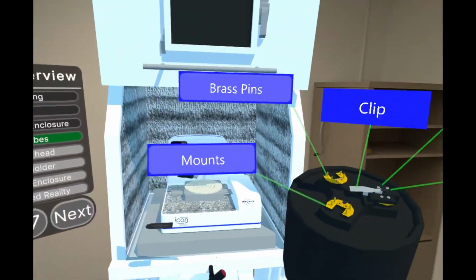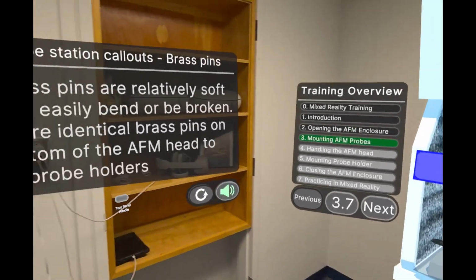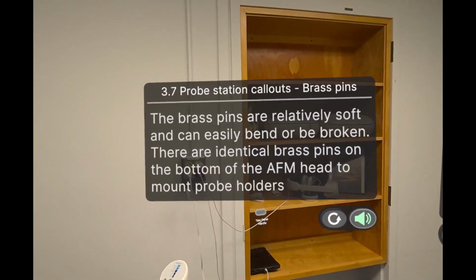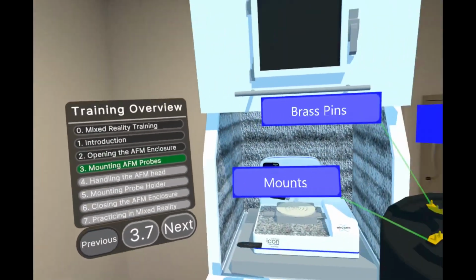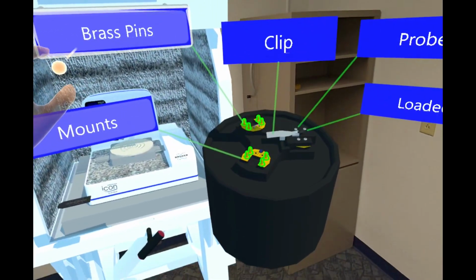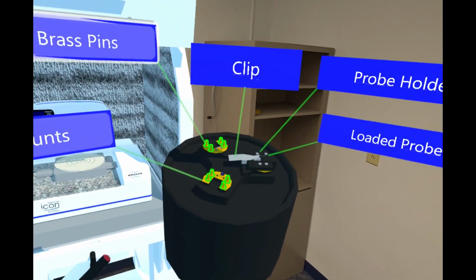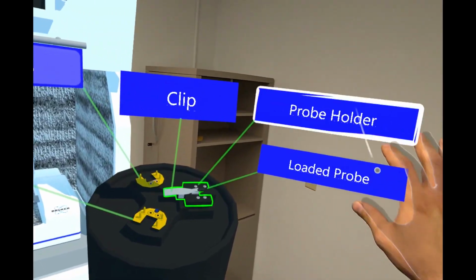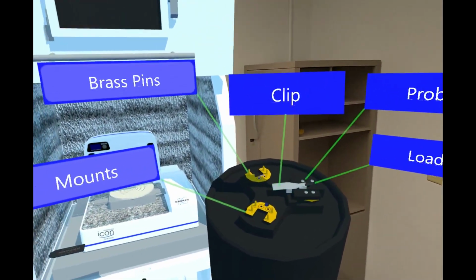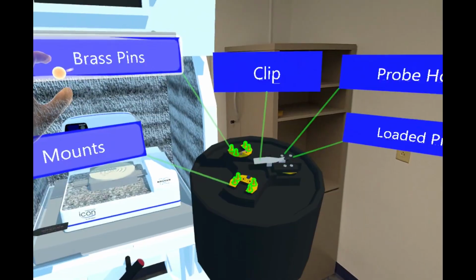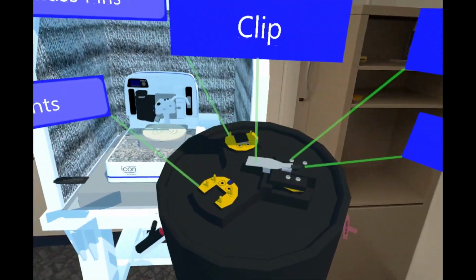The brass pins on the probe station are the same pattern as the pins on the bottom of the AFM head. When you look at the probe holder, you will see 4 holes that line up with these pins. The brass pins are very soft and delicate and are easily bent or broken, so be careful when handling the AFM head and the probe station.